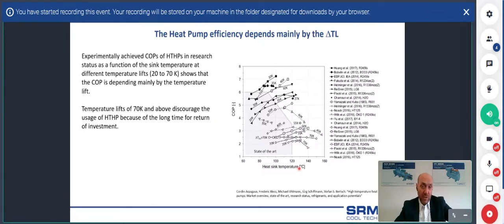We can see how the COP is distributed, and we can see that the higher levels we can normally reach are between 6 and 7 as a COP, while the lower are between 2 and 3. What this graph also indicates is the so-called temperature lift, the difference between the evaporating and the condensing temperature. The lower temperature lift systems can grant higher efficiency, while the higher temperature lift systems, between 60 and 70 degrees Kelvin, are related to a lower COP, so with a lower efficiency.